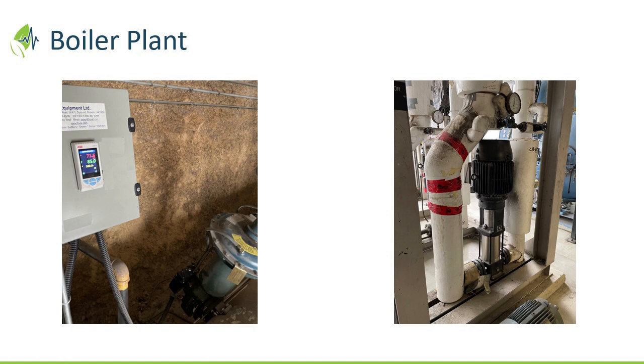Let's go through some more pictures and just pick up anything. This is the feed water pump on the right, right? Yep. And so if you want to, how are you going to shut the condensate off when the boiler is not running? How are you going to stop that condensate going through the economizer so essentially it's giving up heat rather than... So every boiler out there, especially if you're modulating feed water, which the majority in the room are, I've been doing most of your hospitals, but you have to have continuous flow across the economizer to stop flashing, right?